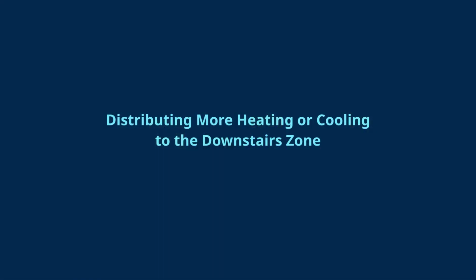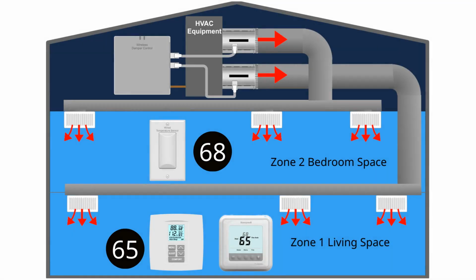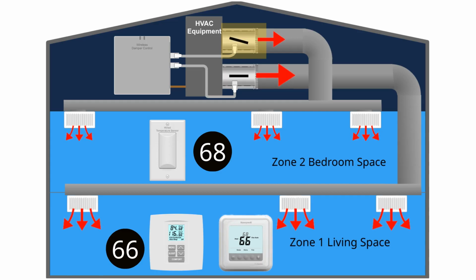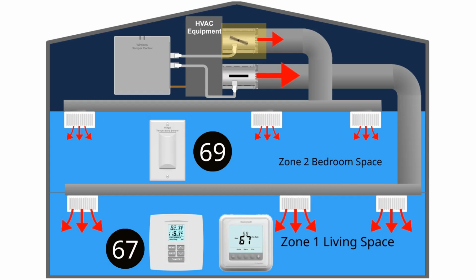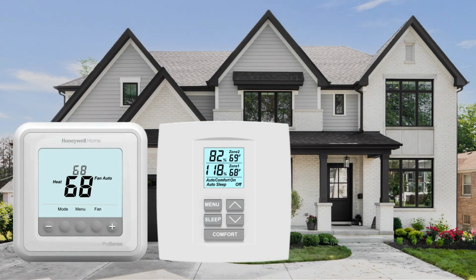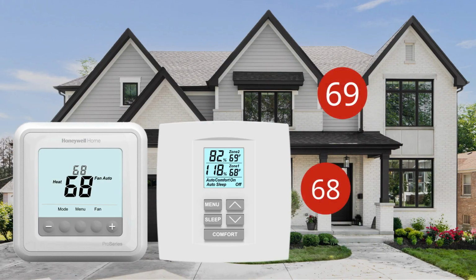To distribute more heating or cooling downstairs, the downstairs damper fully opens and the upstairs damper closes 2% every 2 minutes, forcing more heating or cooling to the downstairs zone, improving comfort downstairs without overheating or overcooling the upstairs. The two-zone comfort control dynamically adjusts the dampers to find the right distribution of heating or cooling to provide a balanced, uniformly comfortable home and save energy in every season.